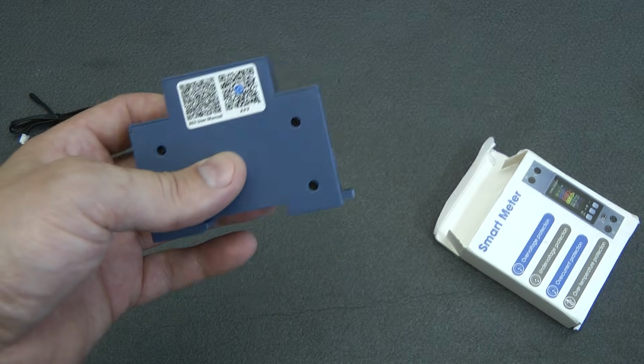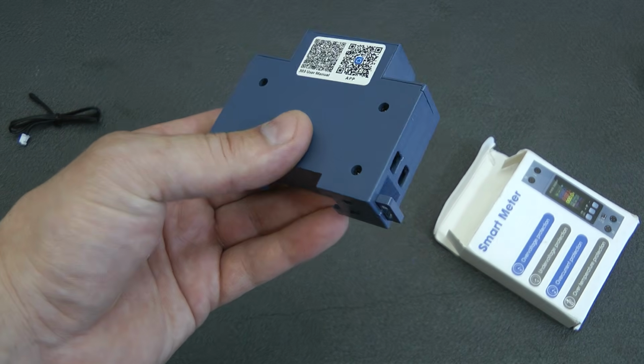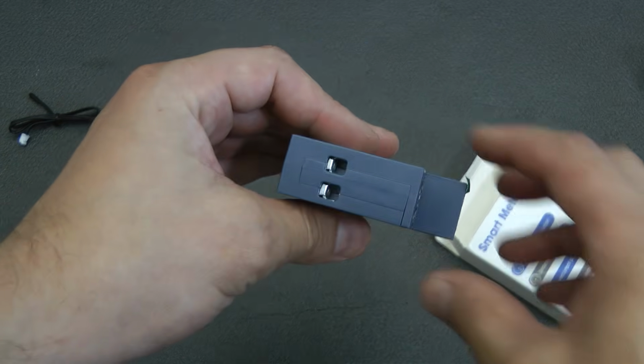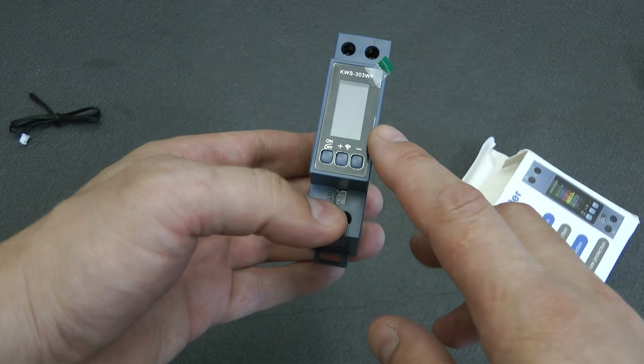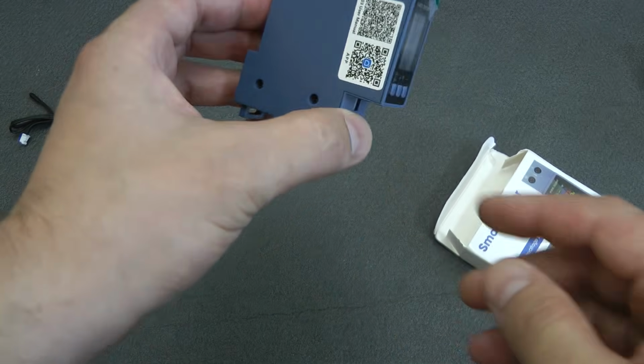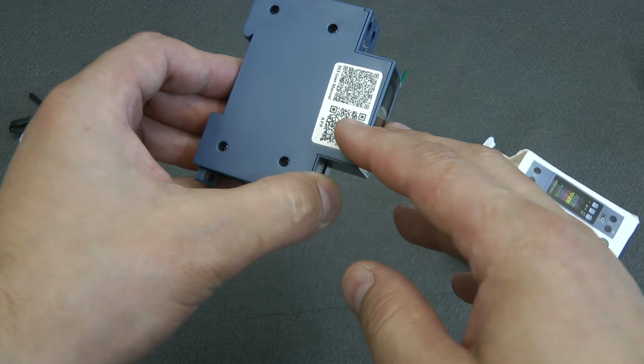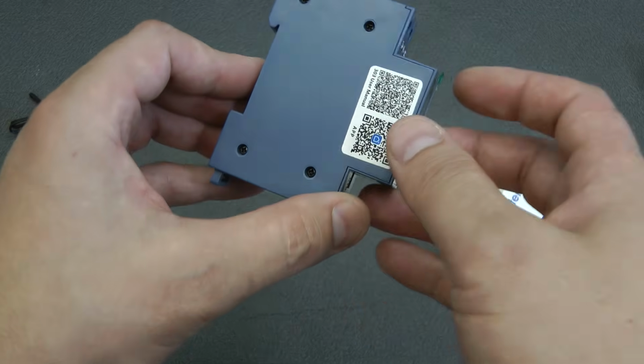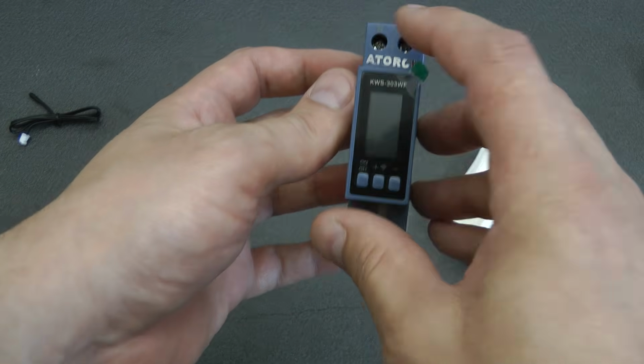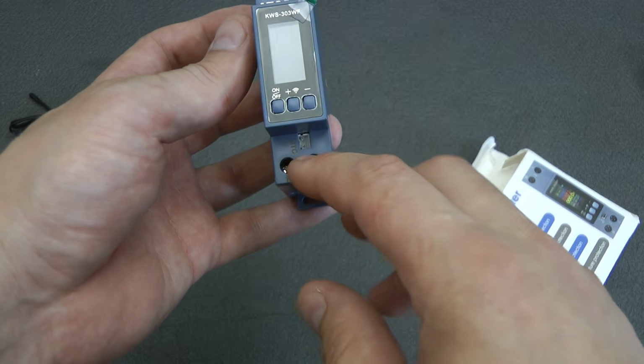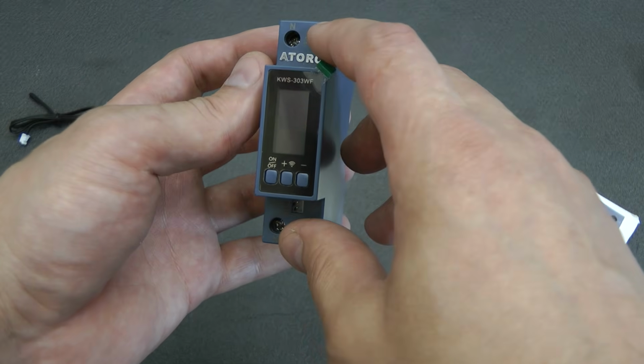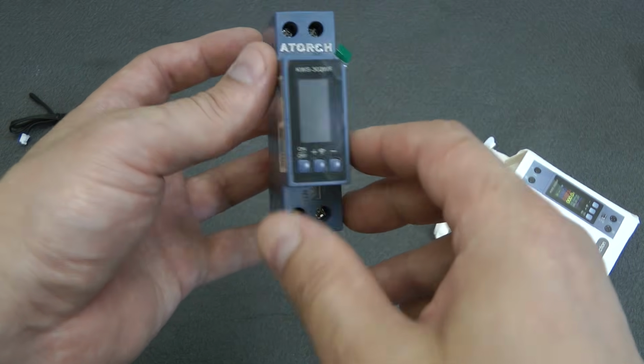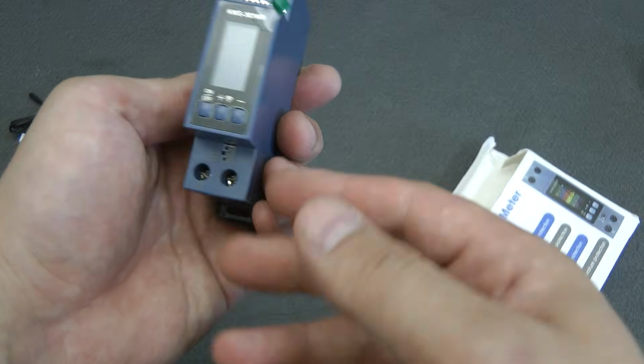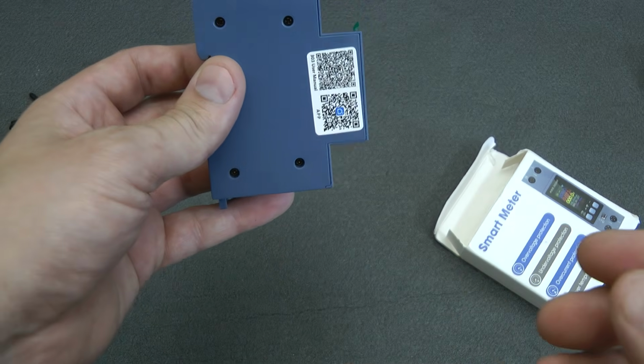In terms of size, the relay is almost no different from a regular circuit breaker and takes 1 DIN position. The differences are the color display and control buttons. On the side edge, there is a QR code for installing the Tuya or Smart Life app. 4 terminals are used for connection. The mains input is at the top, and the output to the load is at the bottom. There are separate contacts for phase and neutral, but what exactly the relay disconnects when switched off, only the phase or both conductors, we will check later.